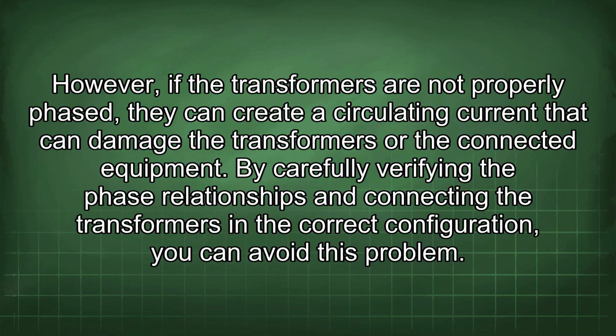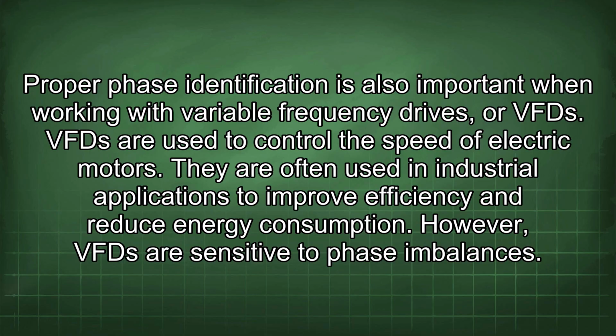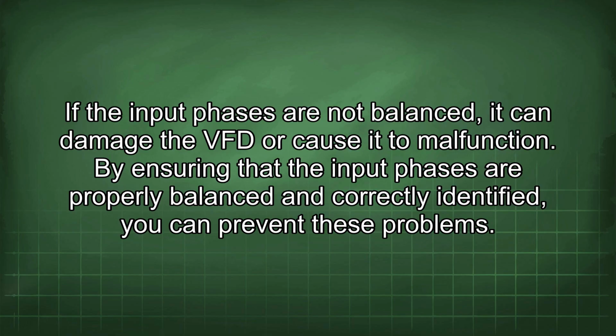Proper phase identification is also important when working with variable frequency drives, or VFDs. VFDs are used to control the speed of electric motors. They are often used in industrial applications to improve efficiency and reduce energy consumption. However, VFDs are sensitive to phase imbalances. If the input phases are not balanced, it can damage the VFD or cause it to malfunction. By ensuring that the input phases are properly balanced and correctly identified, you can prevent these problems.